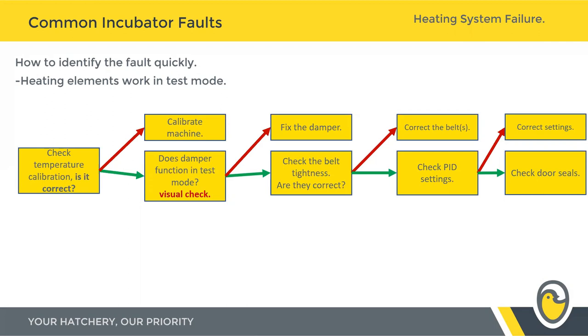Last of all, check the overall integrity of the machine — specifically the door seals. If your door's not closing correctly, even a small gap at the bottom or around the seal on the edges can lead to a massive increase in airflow through the incubator. That can throw the temperature control off inside the incubator, leading to all the problems we discussed — additional heating per zone and an increase in the hatch window.